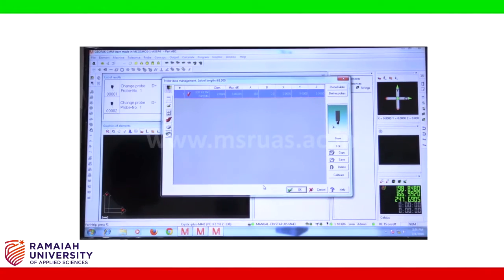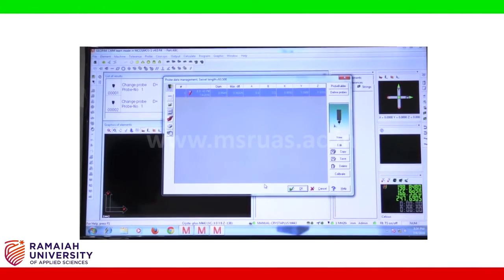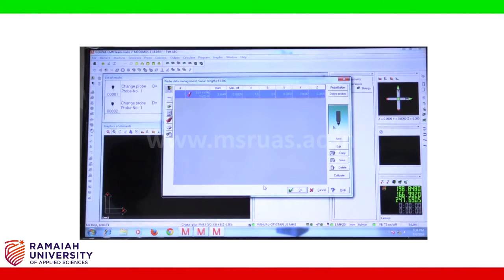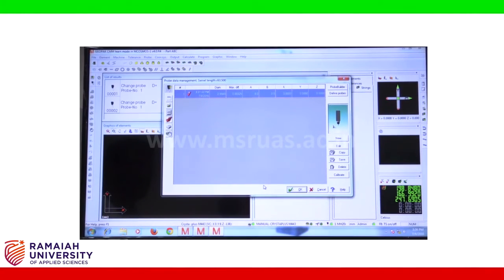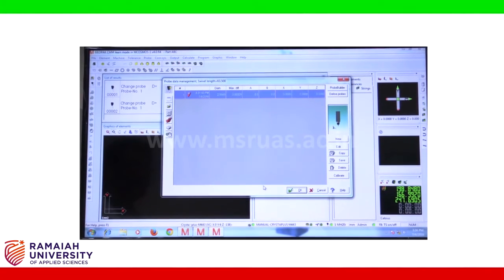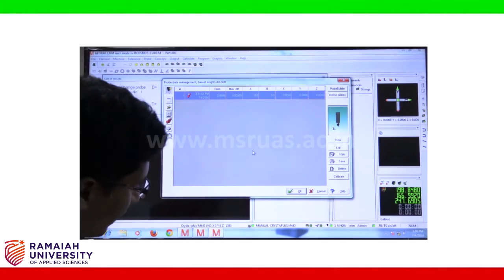Fifth. Now the calibration process is complete, and one can see an error of about 0.00329 millimeters. Now this is quite an acceptable error, since the probe diameter is exactly 3.000, and we have got almost about 3 microns error, and we can use this probe for the measurements. So I am just saying OK. Now the probe is ready for measurements.